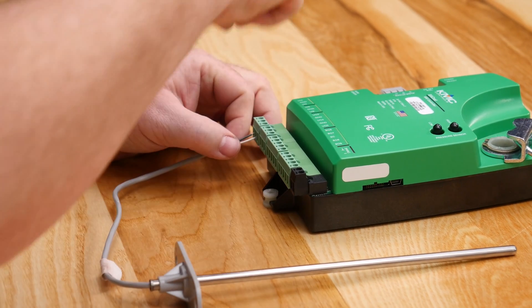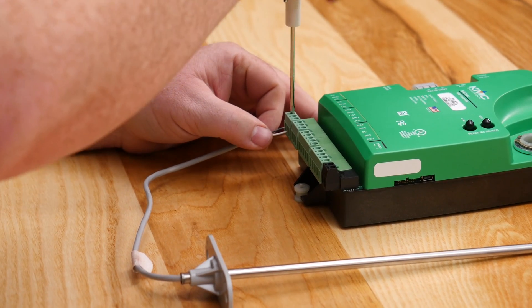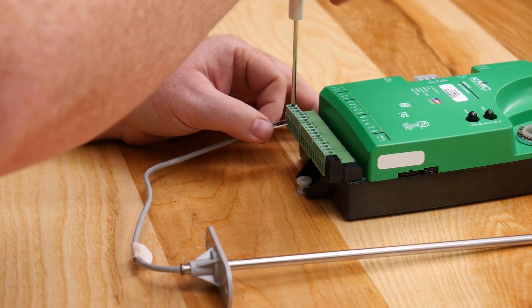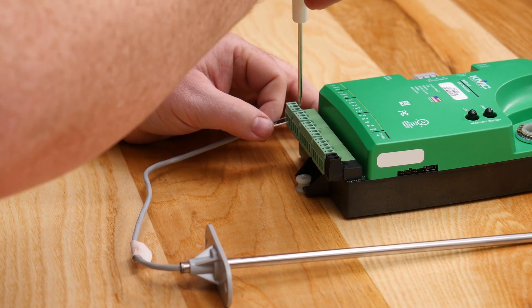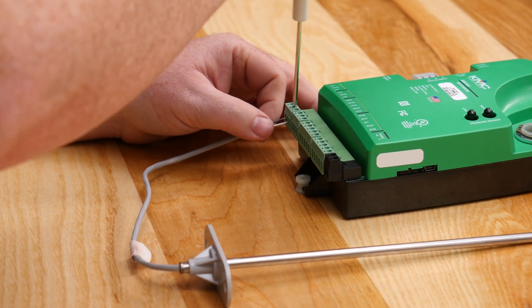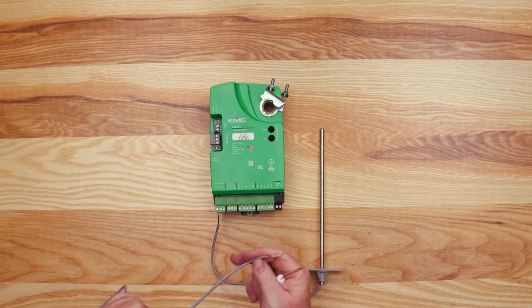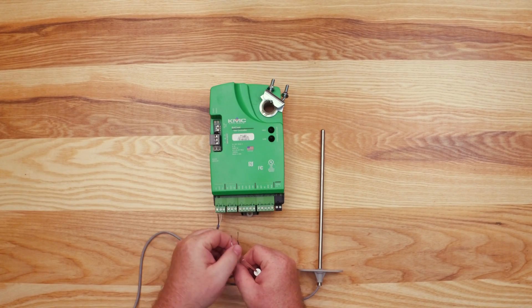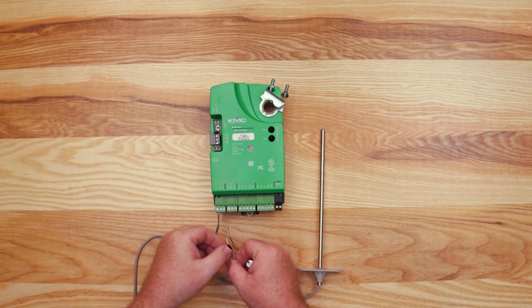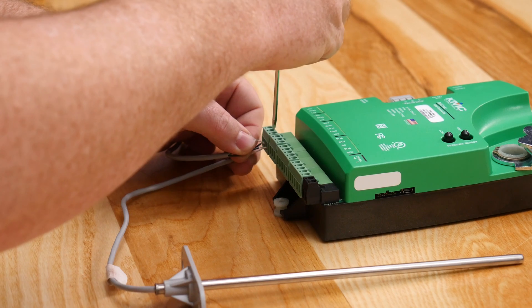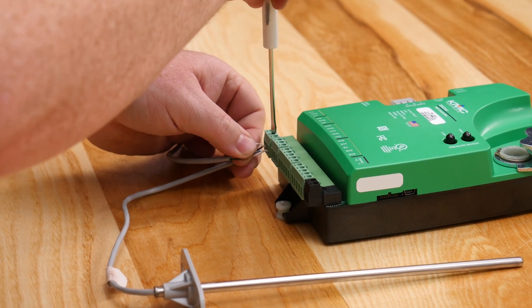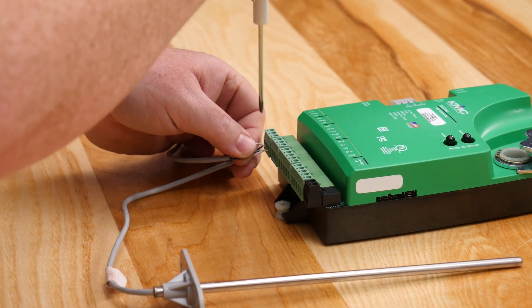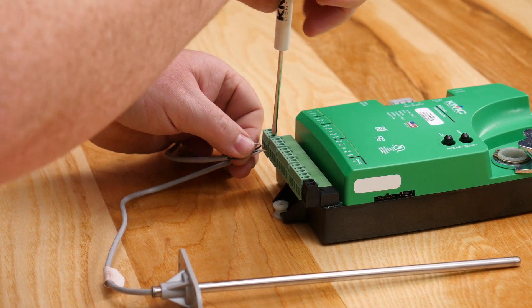Working with the first terminal block, insert the signal wire into the UI3 terminal and the common wire into the adjacent GND terminal. The common wires for inputs in the same terminal block can be grounded together in the same terminal. Thus, the common wire for UI4 can go into the same ground terminal as UI3.